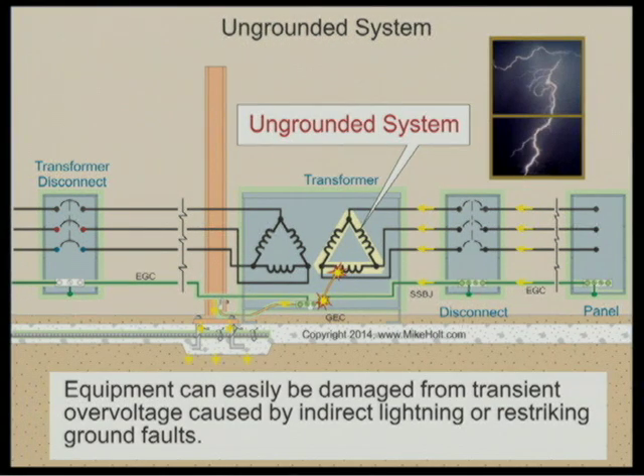Now, one of the problems with an ungrounded system is that equipment can be easily damaged from transient overvoltage caused by lightning or restriking ground faults. Not only that, but there are other cases. So let's take a look at this. Here's a winding with no connection to the earth. Here are insulated conductors. A lightning event outside creates a magnetic field. That expanding and collapsing magnetic field induces and puts pressure on the conductors, which then puts pressure on the system, and that energized charge is attempting to get to the earth. And so it can cause a discharge, and what it does is it causes premature failure of electrical equipment.